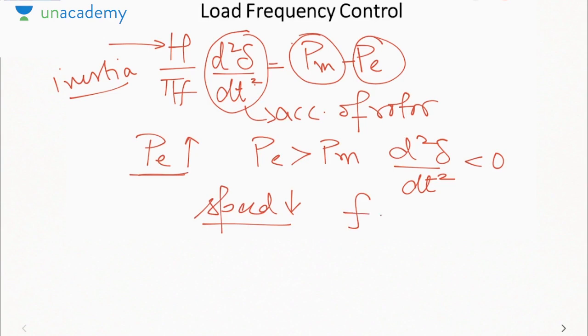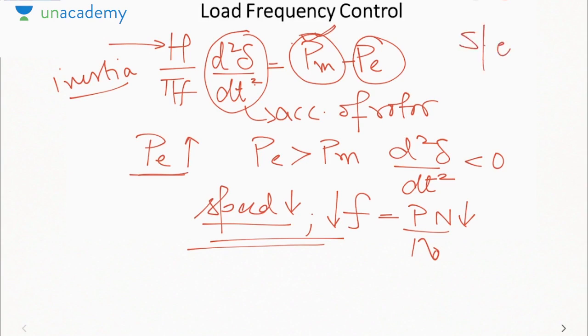And we know frequency of a synchronous generator is Pn by 120. If speed reduces, then frequency also reduces. So to maintain the frequency of the system, we must increase Pm as Pe increases. This is done by means of a speed governor. Okay. It will increase the mechanical input of the machine in accordance with the electrical output to maintain the frequency.